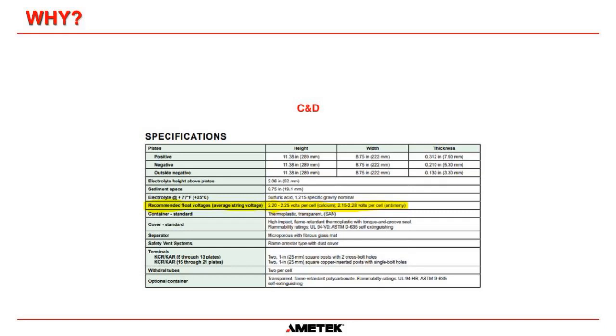Clint's asking, how long should we equalize the string for? Ooh, another great question, and it's very complicated, but if you follow the manufacturer's guidelines, what you're supposed to do is put your charger on equalize and monitor the current with an amp clamp. And then once the current going to your battery has not changed for, I think it's a 3-hour period, but you'd have to read the manufacturer's guidelines on this. Basically it's called current stabilization. Once the current into the battery has stabilized for a prolonged period of time, that is when your equalized time starts. And then every manufacturer has a different amount of time that they recommend their cells to be equalized for.